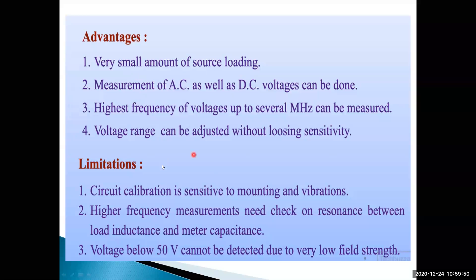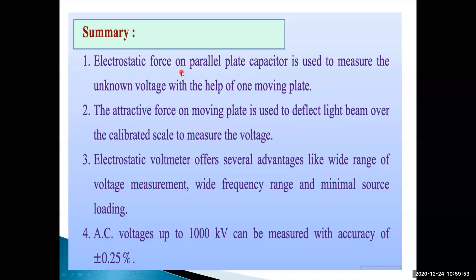Summary: electrostatic force on a parallel plate capacitor is used to measure unknown voltage with the help of one moving plate. The attractive force on the moving plate is used to deflect a light beam over a calibrated scale to measure voltages. The electrostatic voltmeter offers advantages like wide range of voltage measurement, wide frequency range, and minimum source loading. The AC voltage range up to 1000 kilovolts can be measured with accuracy of plus or minus 0.25 percent.